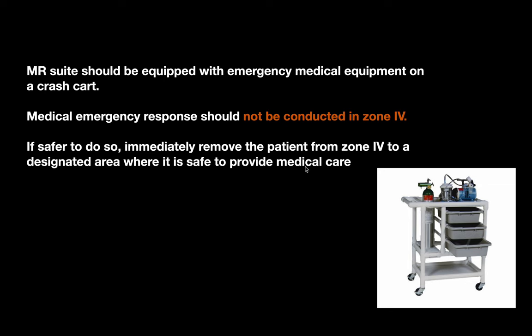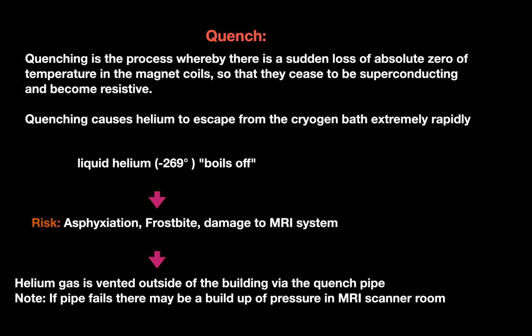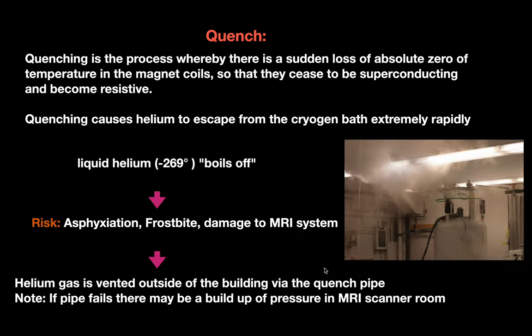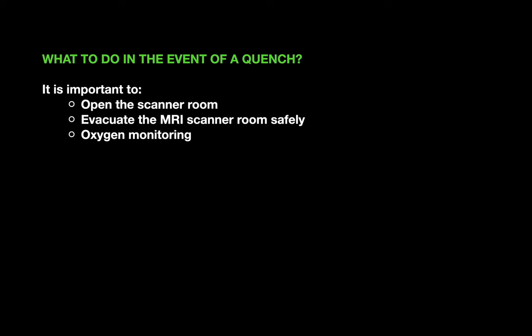Quenching is the process whereby there is sudden loss of absolute zero temperature in the magnetic coil — a sudden loss of the magnetic field in the superconducting magnet due to rapid warming. This can occur if the cryogenic system fails. The release of stored energy during quenching can be hazardous and may damage the magnet and surrounding equipment. Risks include asphyxia and frostbite. Helium gas is vented outside of the building via a quench pipe; if the pipe fails, there may be a pressure buildup in the scanner room. In such an event: open the scanner room, evacuate safely, and perform oxygen monitoring.